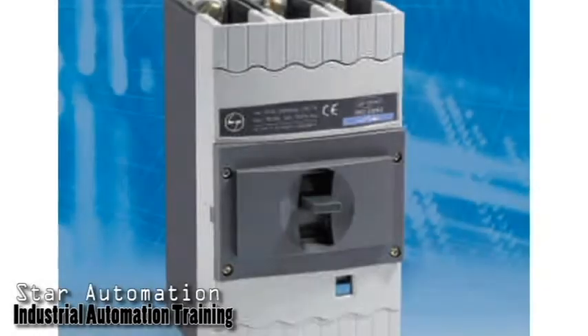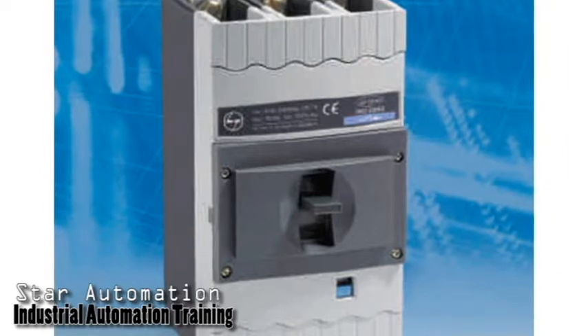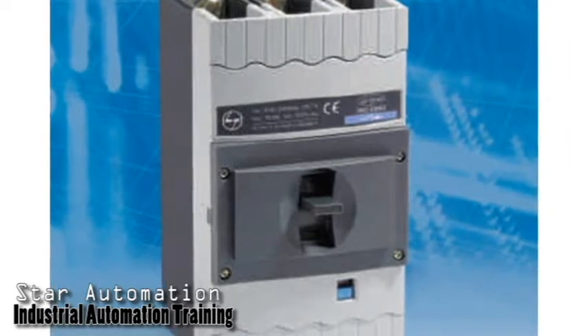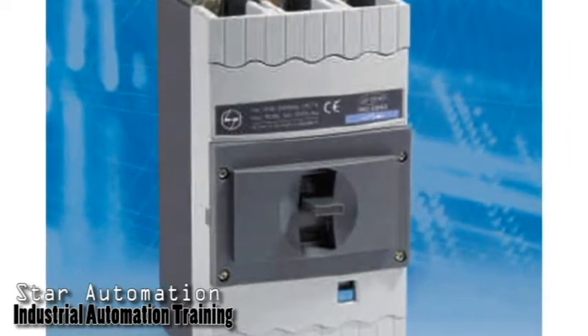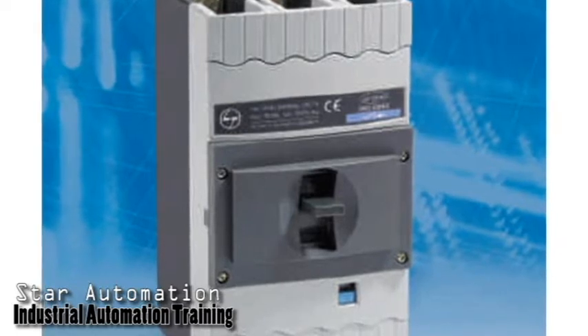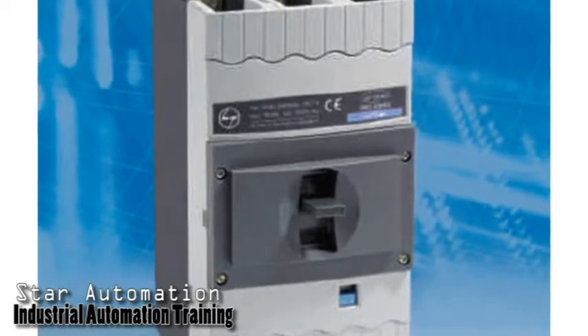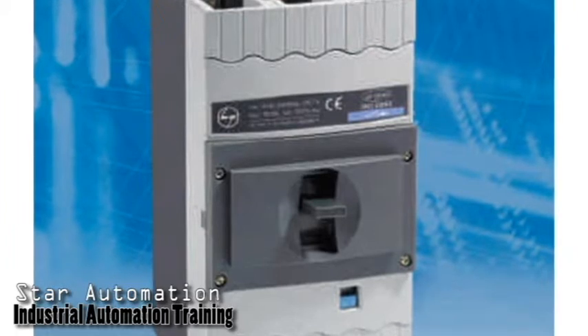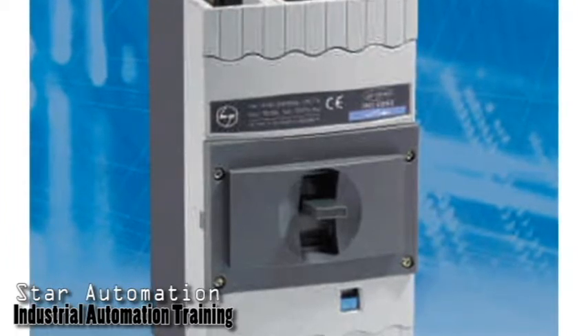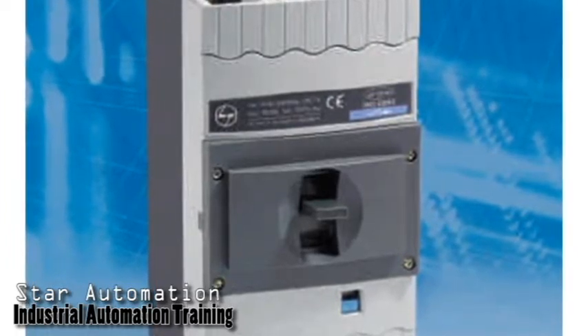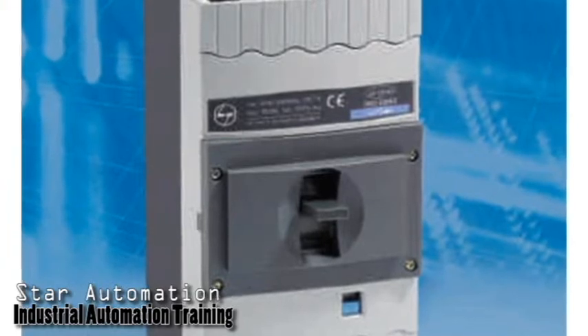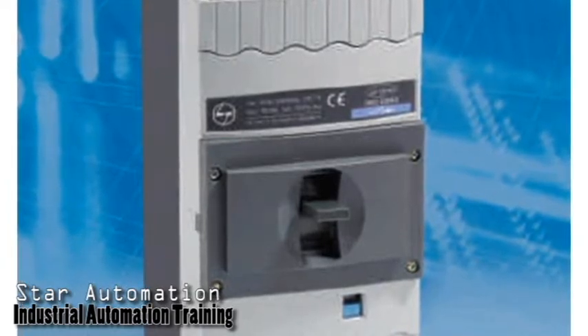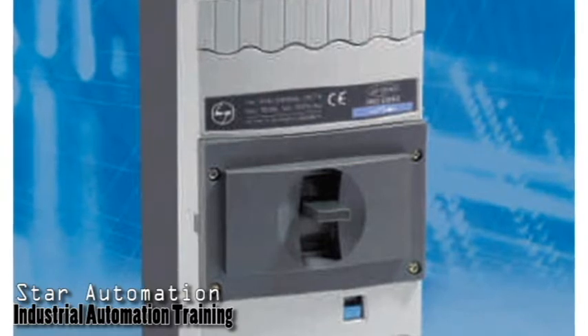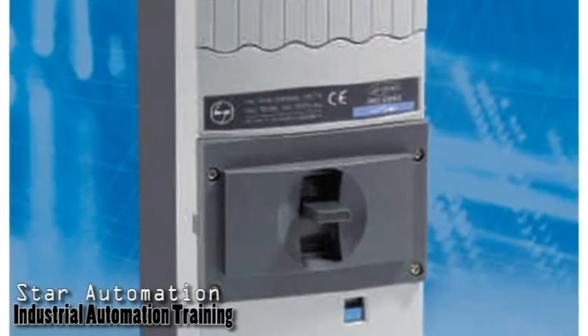Molded case circuit breakers are electromechanical devices which protect a circuit from overcurrent and short circuit. They provide overcurrent and short circuit protection for circuits ranging from 63 amps up to 3000 amps. MCCB is an alternative to a fuse since it does not require replacement once an overload is detected. Unlike a fuse, an MCCB can be easily reset after a fault and offers improved operational safety and convenience without incurring operating cost.